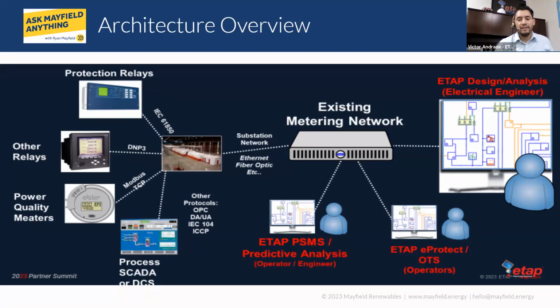Here we have ETAP on the right-hand side. That's the design and the analysis tool. It does have the drivers and the connectivity to connect to an existing metering network. This could be a power monitoring or SCADA system. We're vendor agnostic, and connect directly to equipment like protection relays. And using a module like eProtect, the protection engineer can read protective device settings, perform the protection study we talked about earlier in ETAP, and then send the protective device settings back to the protection relay. Again, minimizing human error and making your job a lot easier, right? With fewer errors.